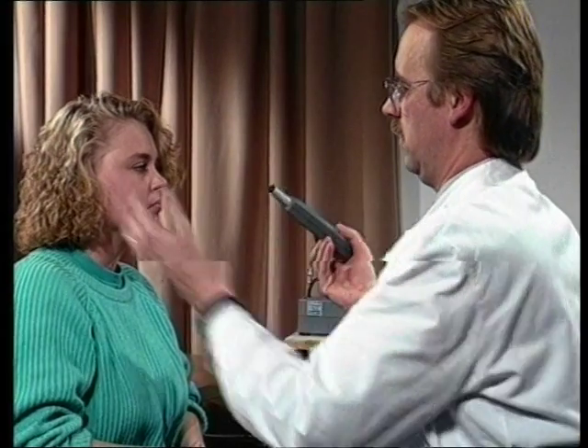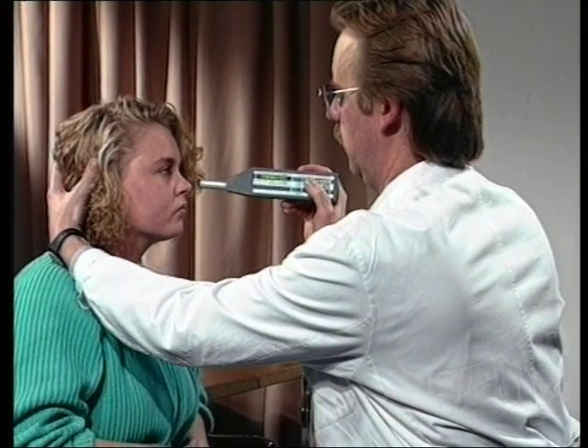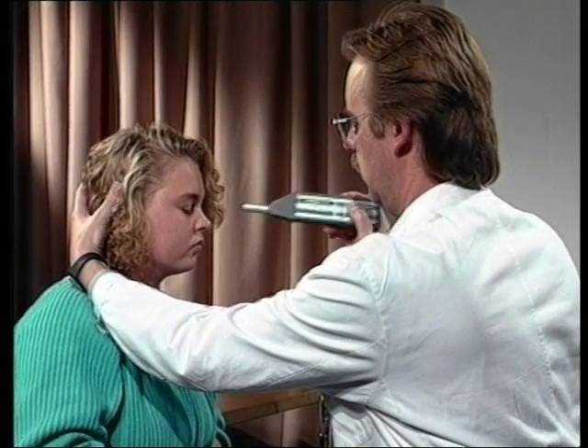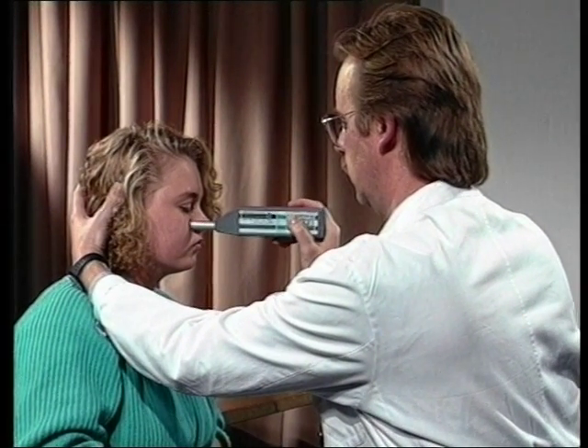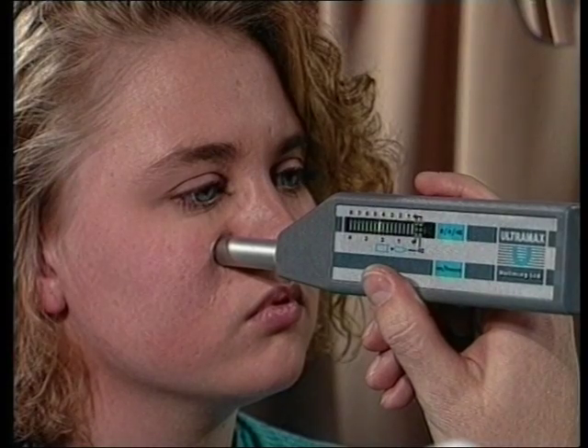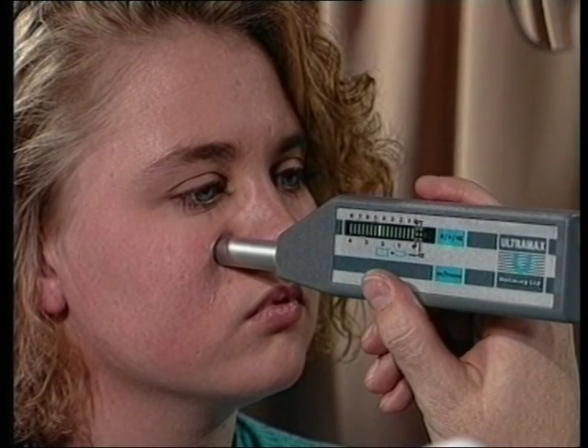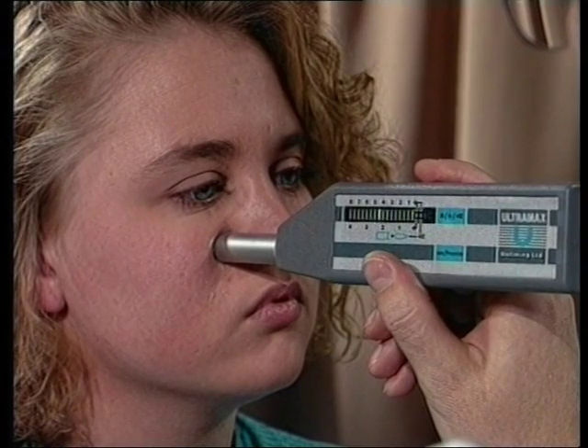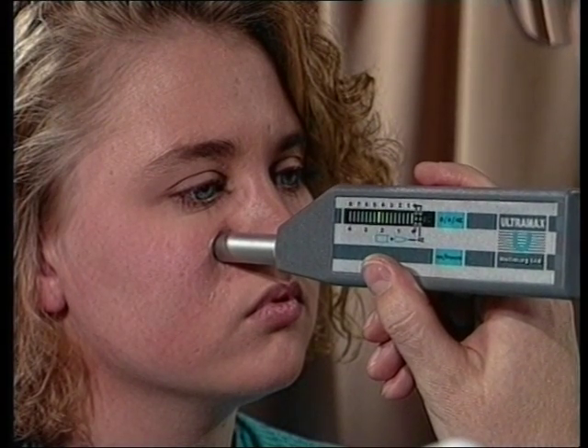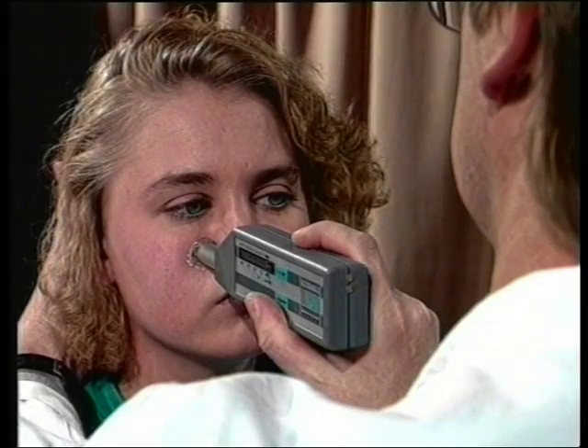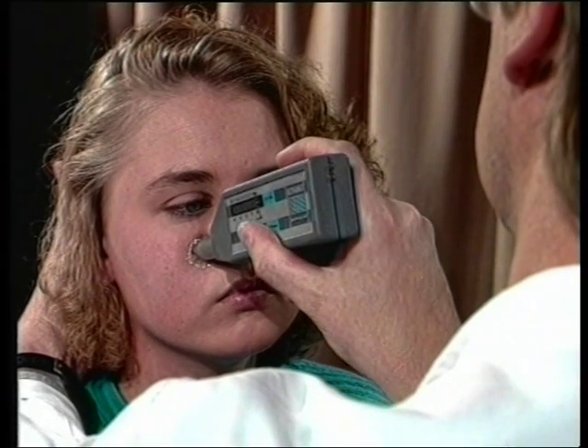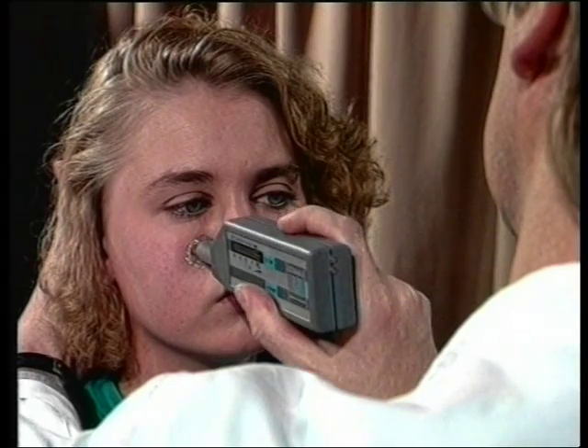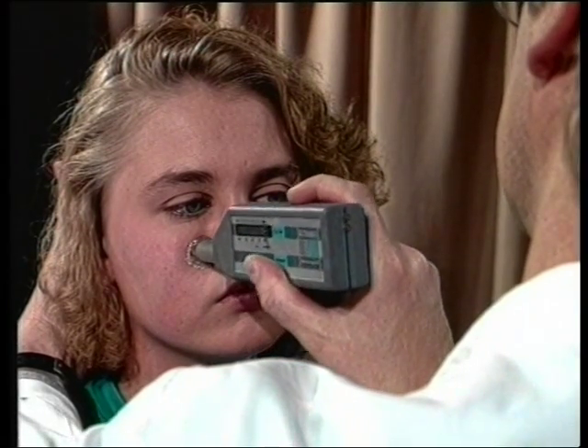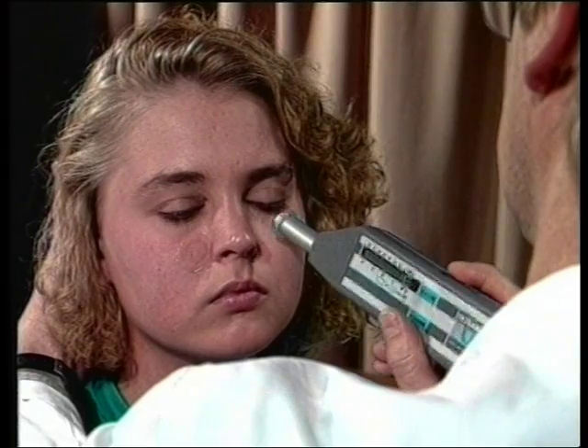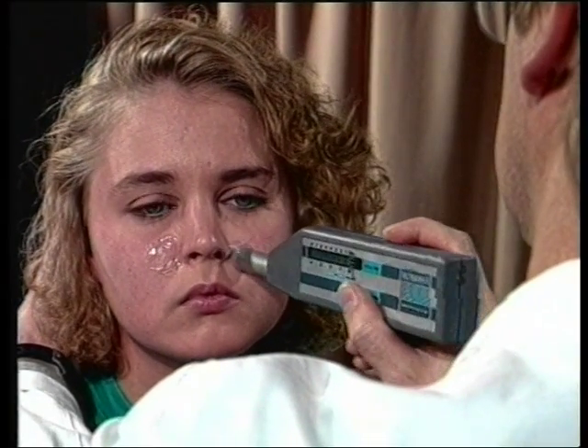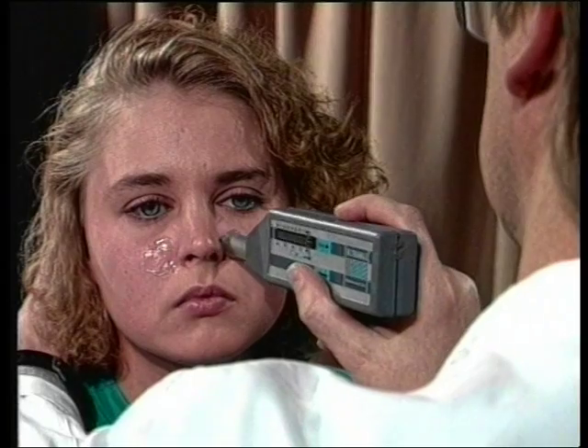When examining the maxillary sinuses of adults, the patient's head must be held in an upright position. The tip of the probe is pressed tightly against the anterior wall of the sinus. The lower margin of the probe should be level with the base of the nasal cavity, with the probe itself gently touching the side of the nose. Special attention should be paid to keeping the tip of the probe tightly against the anterior wall. False back wall echoes may be found if the probe glides to the orbit area, the lateral or medial walls of the sinus.